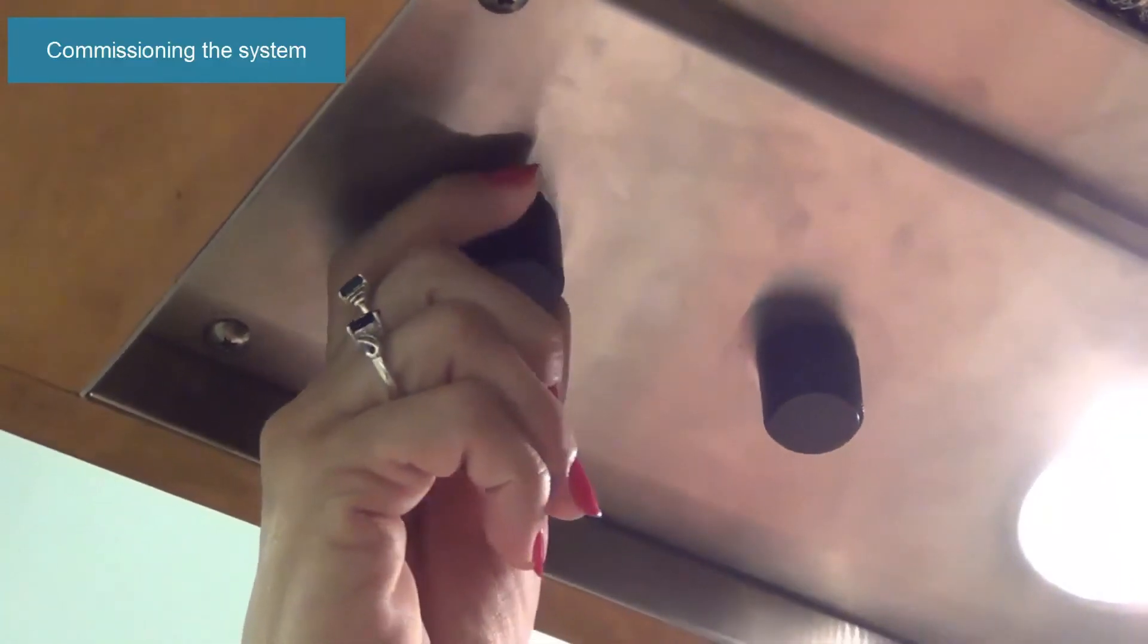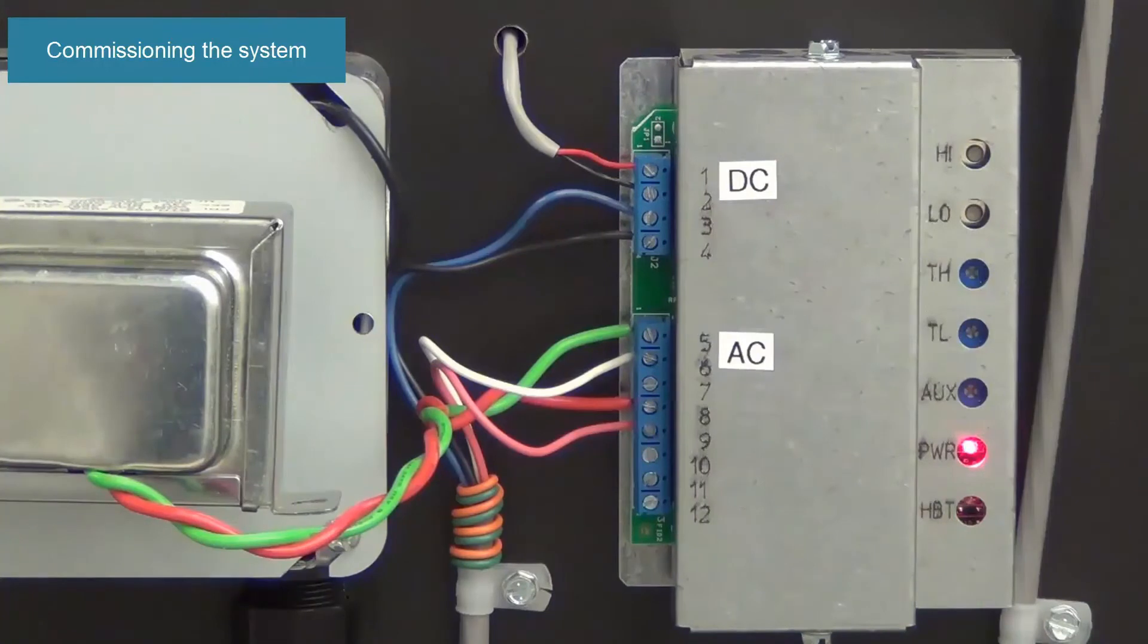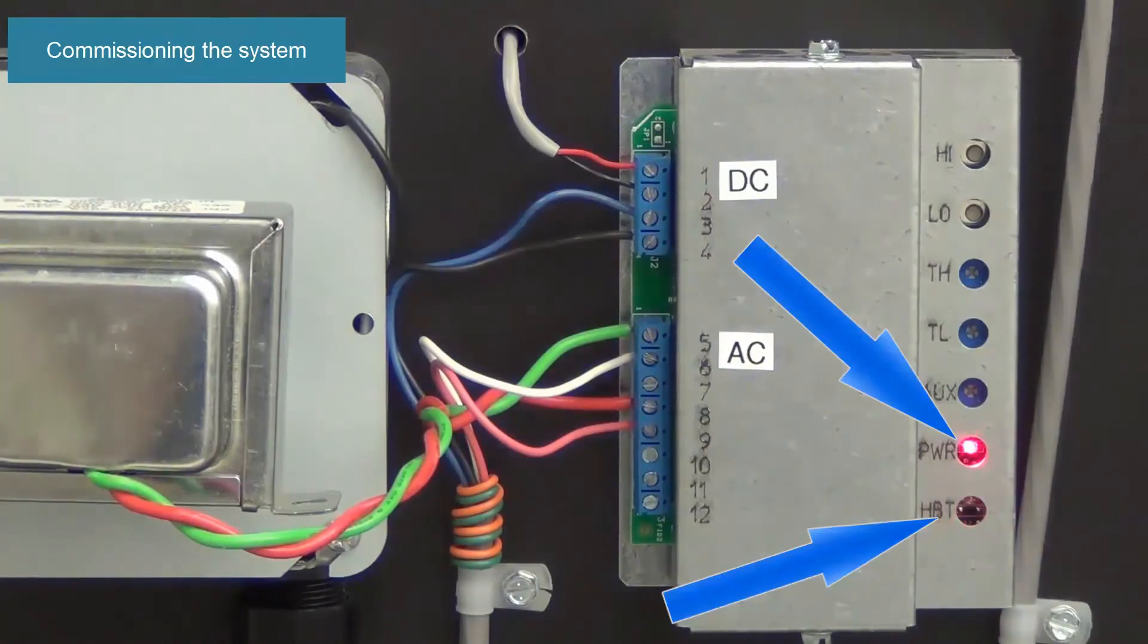Turn on the power to the exhaust fan, make up air fan and if installed, the heater. On the controller, there will be a steady red power light and a pulsing heartbeat LED to indicate the control is energized and ready for programming.